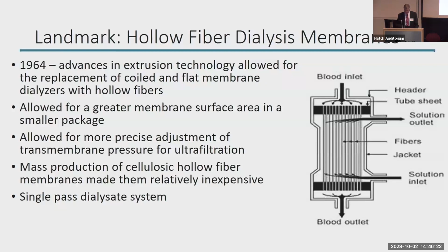So in terms of the convenience and the ability of nurses to take them on and take them off, it was definitely a major advance. It also allowed for more precise adjustment of the transmembrane pressure for ultrafiltration because it was a completely closed system, and all of the mechanics of the pressures on the arterial and the venous side were pretty much regulated by the dialysis machine. And ultimately, the mass production of these hollow fiber membranes made them relatively inexpensive; the cellulosic membranes were about $10 a piece. And if you remember from Kevin's presentation, the reimbursement for dialysis was somewhere around $130. That included what was called the composite rate. So it was economically feasible to take a $10 cellulosic hollow fiber membrane and throw it away at the end of the treatment and then use a brand new one at the beginning of the next treatment.